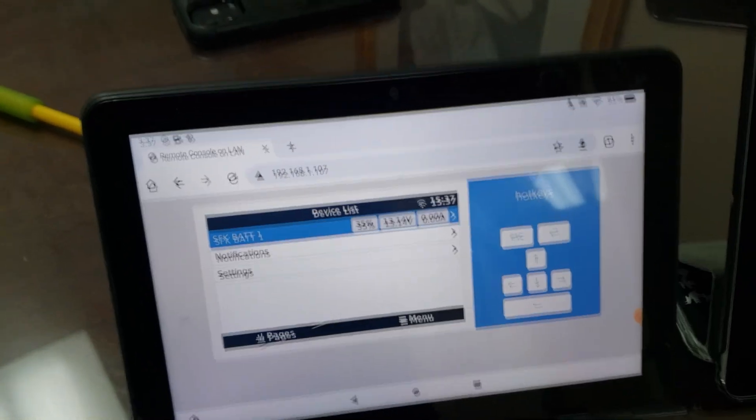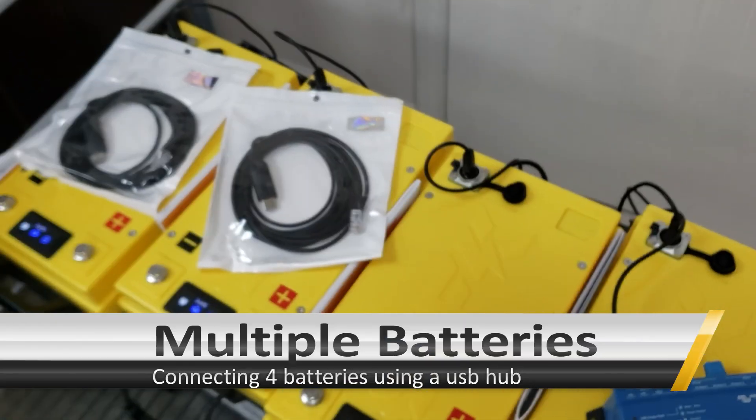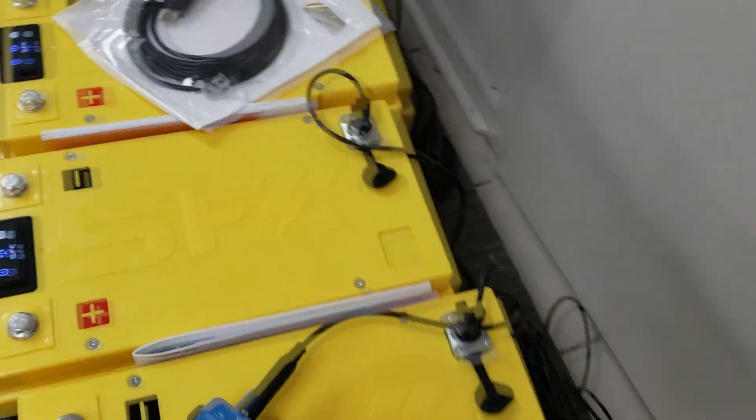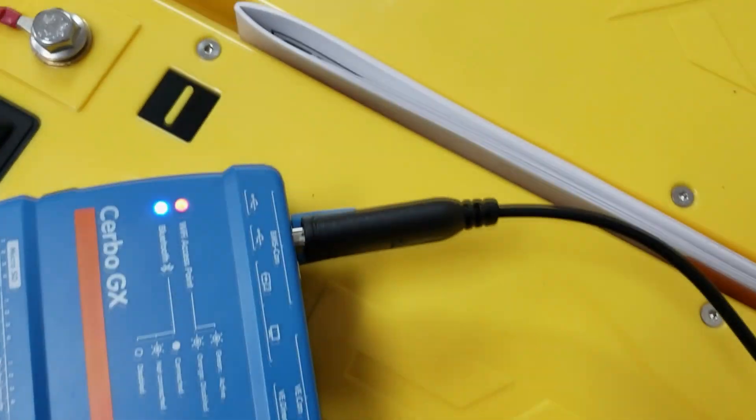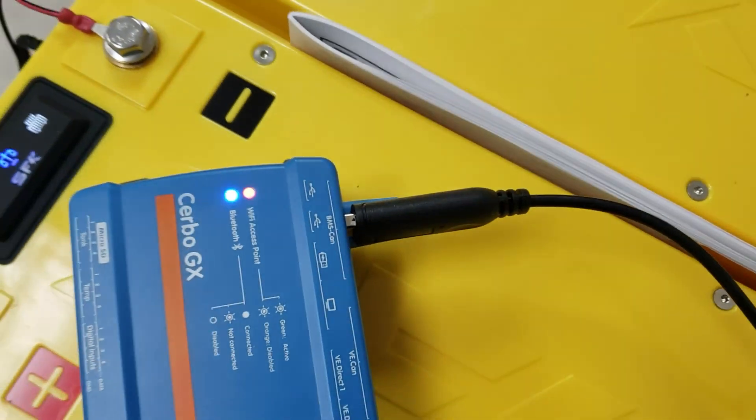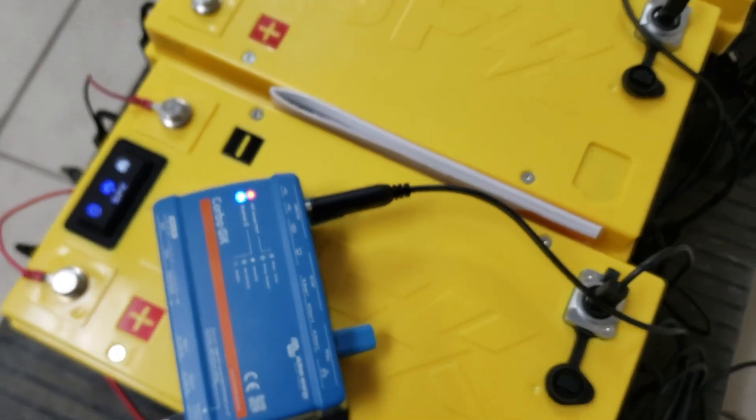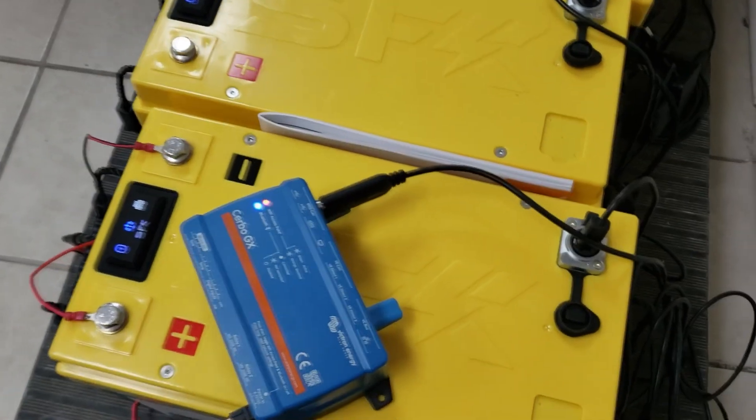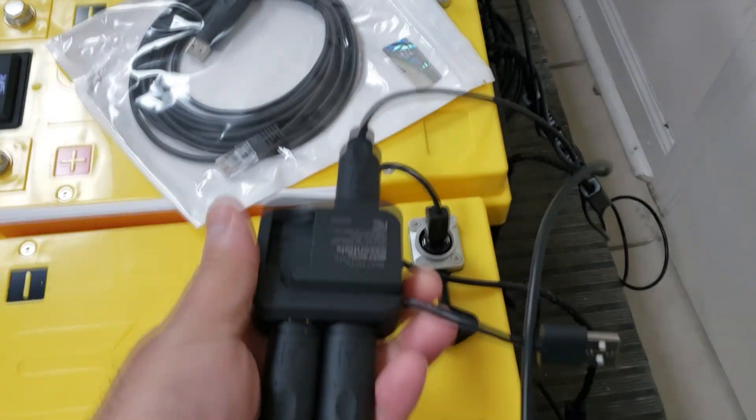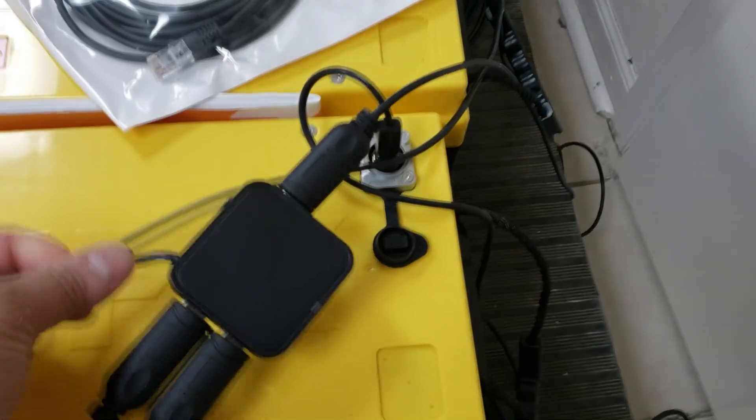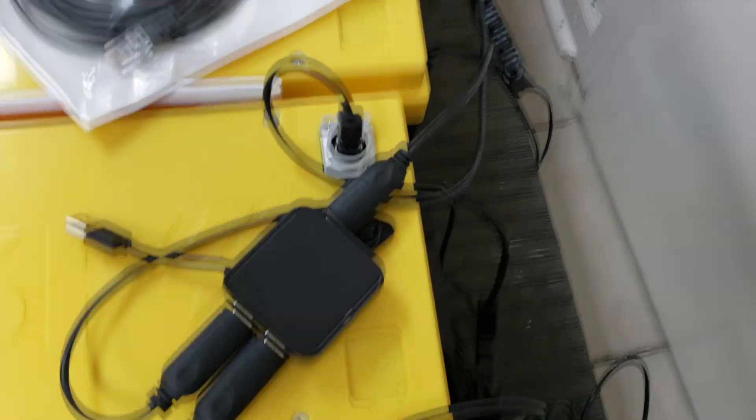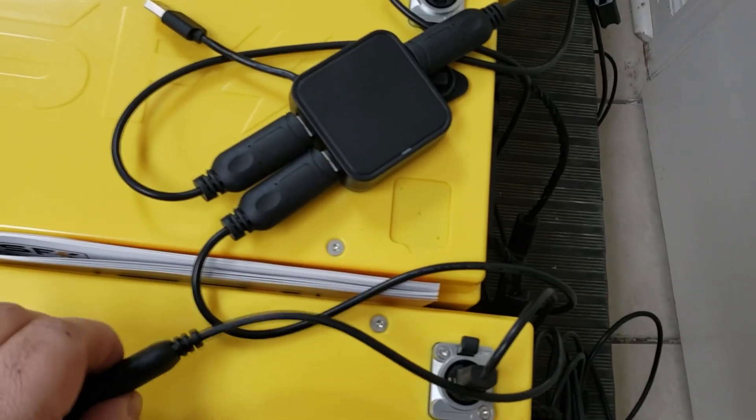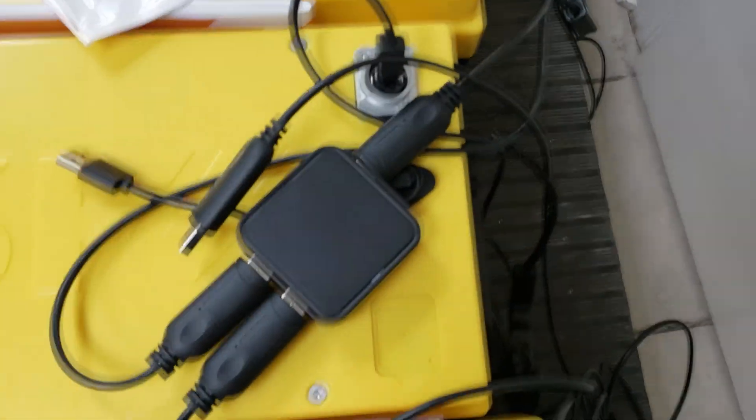So that's how you install one battery, good. But we all know people have more than one battery, so what do you do if you have multiple batteries? Now there are two ports on the Cerbo so you could put up to two of them connected directly to it and that will give you two batteries. But again, people have multiple batteries, so for that we can get a basic USB hub. It doesn't have to be a powered USB hub, it can just be a basic USB hub. You can see we've connected the three batteries there. We're actually going to disconnect this battery here and also connect it to this hub so we'll have four.